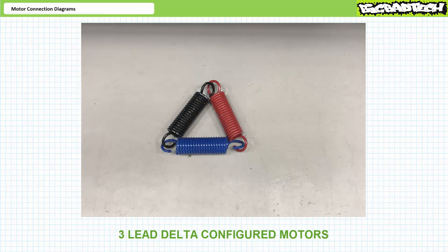One can say nearly the exact same thing about three-lead delta-configured motors. These motors are permanently pre-configured as deltas and there's nothing you can do about it. Electrically, one might visualize three separate windings bonded together in a delta fashion. Three external leads at the corners — one, two, and three — allow connection to primary voltage L1, L2, and L3. Swapping any two applied phase sequences reverses rotational direction.